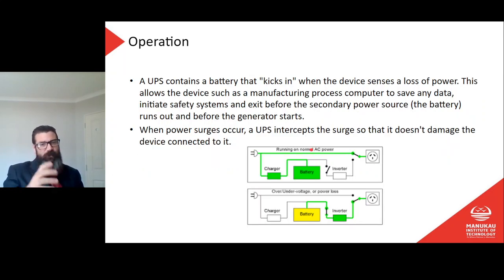Okay, so a UPS contains a battery that kicks in when the device senses a loss of power. This allows the device, such as a manufacturing process computer, to save any data, initiate safety systems, and exit before the secondary power source, that's the battery in the UPS, runs out and before the generator starts. So we might have that lag time between mains and then battery of the UPS and the generator.